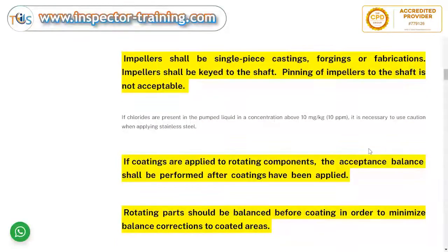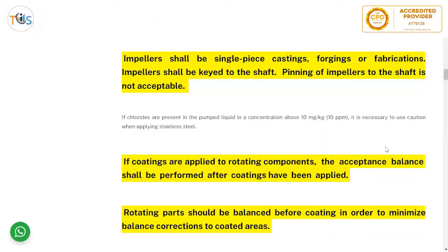Impellers shall be single-piece castings, forgings, or fabrications. Impellers shall be keyed to the shaft; pinning of impellers to the shaft is not acceptable because if the pin breaks the whole assembly collapses. Keying is far more reliable than pinning.